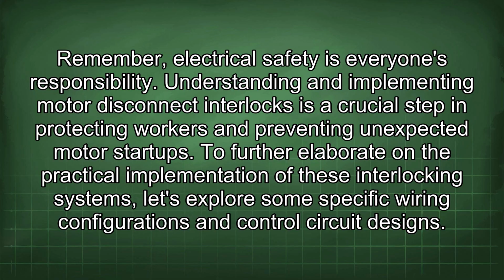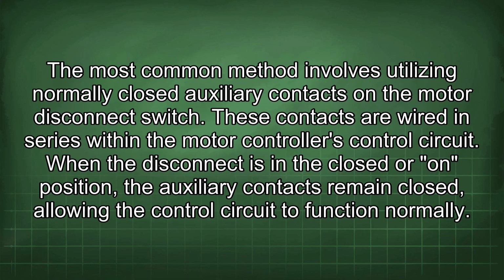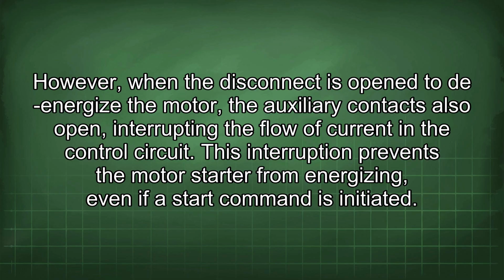To further elaborate on the practical implementation of these interlocking systems, let's explore some specific wiring configurations and control circuit designs. The most common method involves utilizing normally closed auxiliary contacts on the motor disconnect switch. These contacts are wired in series within the motor controller's control circuit. When the disconnect is in the closed or on position, the auxiliary contacts remain closed, allowing the control circuit to function normally. However, when the disconnect is opened to de-energize the motor, the auxiliary contacts also open, interrupting the flow of current in the control circuit. This interruption prevents the motor starter from energizing, even if a start command is initiated.